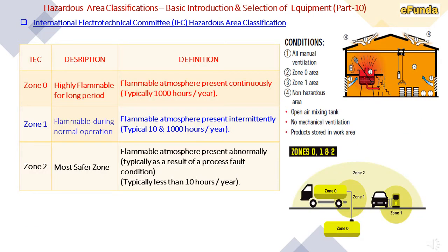IEC hazardous area classification: Zone 0 is a highly flammable zone where a flammable atmosphere is present continuously, typically 1000 hours per year. Zone 1 is flammable during normal operation with the atmosphere present intermittently, typically in the range of 10 to 1000 hours per year. Zone 2 is the most safe zone where a flammable atmosphere is present abnormally, typically as a result of a process fault, typically less than 10 hours per year.